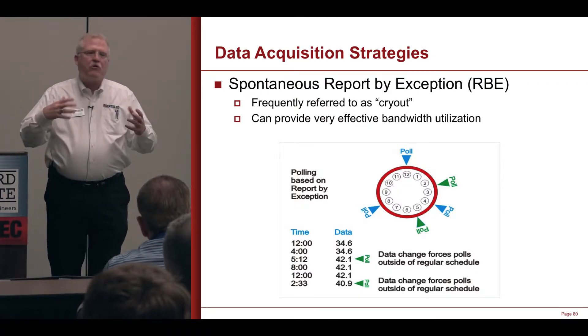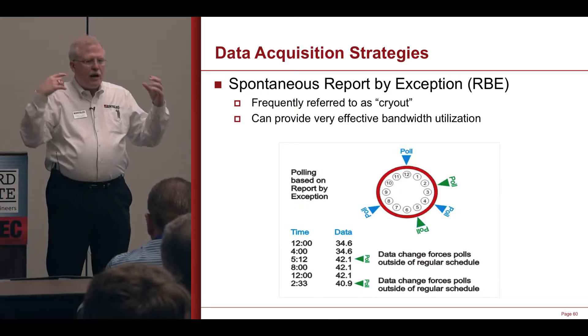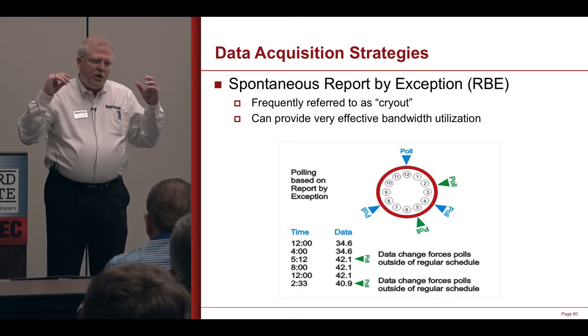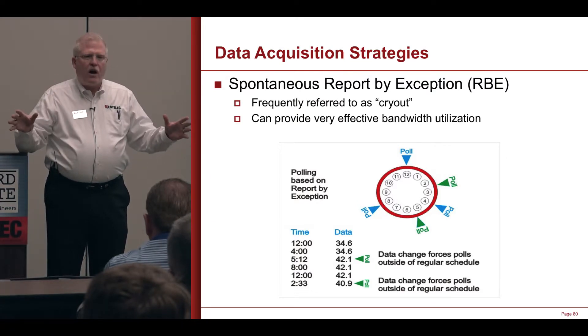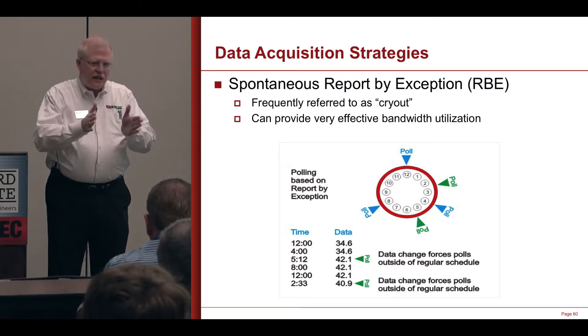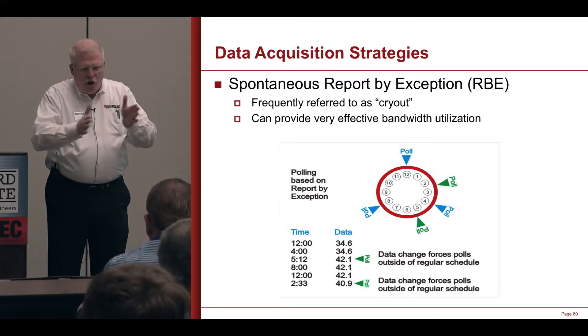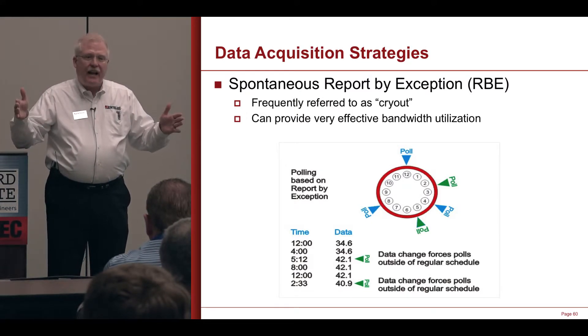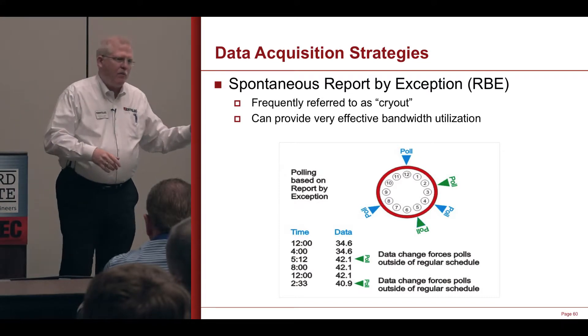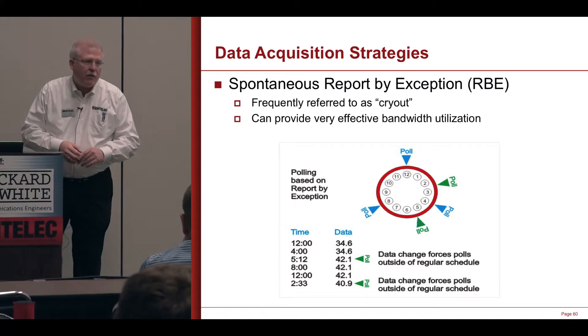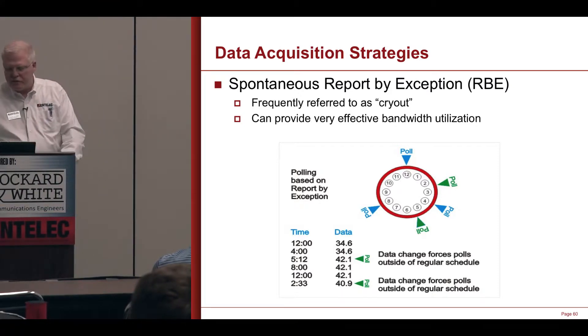Think about this: in electrical power, if I'm monitoring stuff inside of a switch station, when nothing's going on I get no data back. But if I get a trip, I want — in a millisecond time frame — all the data that changed when that trip occurred, so I can analyze what occurred. So these report by exception protocols are proliferating in electric power utilities for that reason.